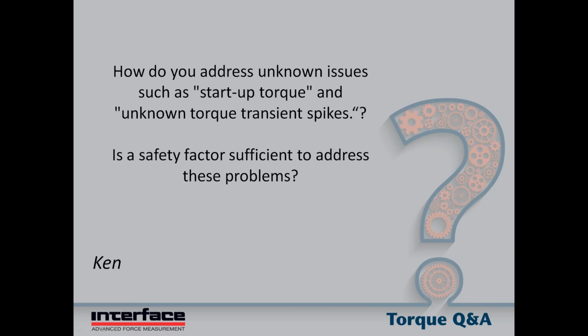And so torque sensors always have a safe overload range, but that overload range should be reserved only for accidental use. So that's number one. Number two, torque sensors usually have limits on how high they can go as far as the measurement, and that may be quite a bit less than the actual safe overload. In many cases, it's 10 or 20% above capacity. So if this transducer is sized, say, around the average running torque and the spikes are going up above that, you can't actually necessarily even tell because they'll basically be exceeding the measuring range of the sensor electronics and the signal clips. You may not know it, so you have to be real careful to size the sensor appropriately.